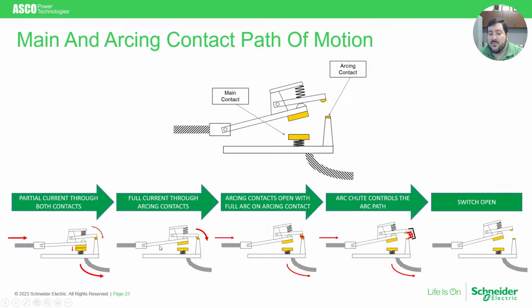And for a very brief period of time, all the electrical flow will be flowing through the arcing contact because it will still be in a closed position. The main contact opens first, then the arcing contact. As the arcing contact then begins to open, it will draw the arc upon it, but that is the entire point of the arcing contact. It is protecting the main contact, which is usually the piece that's conducting most of the current, is drawing the arc towards it and then flowing through the arc chute, which I will show in more detail on the next slide, until the arc is extinguished.